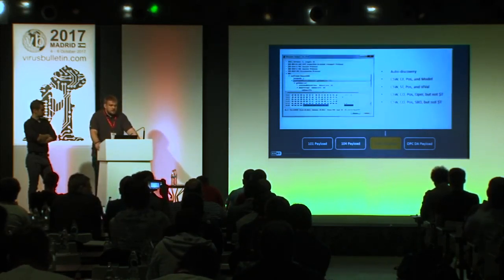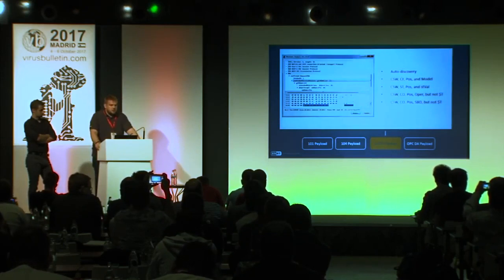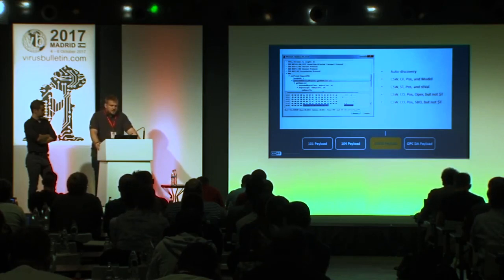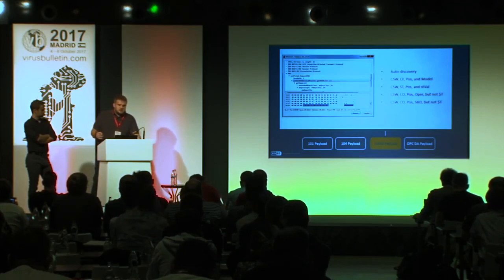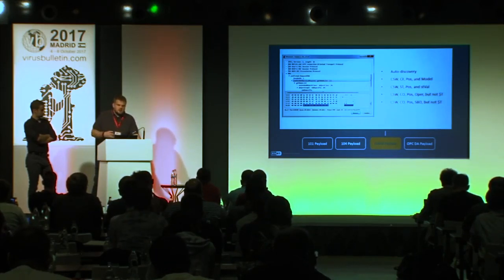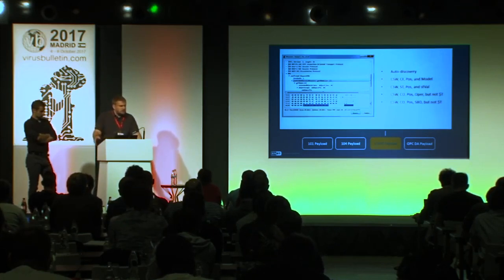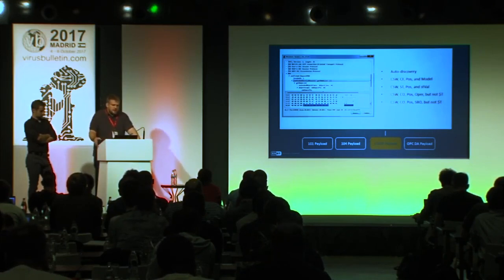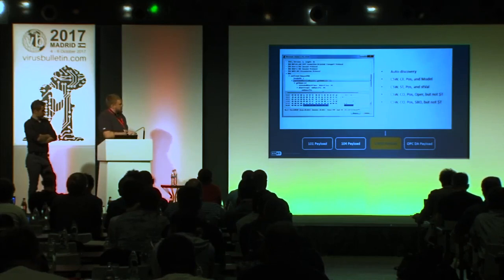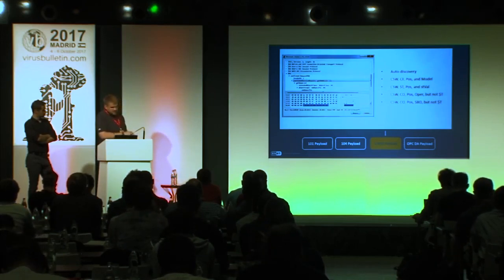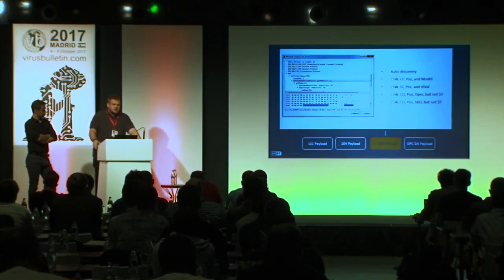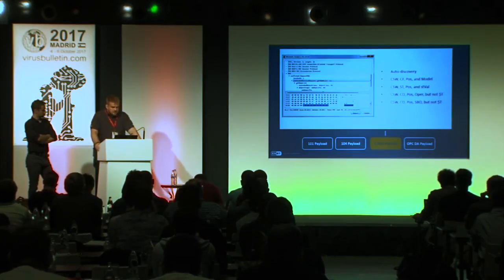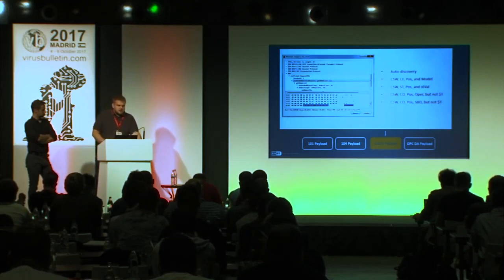61850 is a bit different and a bit more advanced. Like 104, it operates over TCP/IP, but it functions even if an IP address is not defined in the configuration. It has auto-discovery features, so it can discover these devices in the network. It does not operate on IOAs, but on named elements. It looks for hard-coded names, and they correspond to circuit breakers and switches. So it's a different approach, but the same purpose: to open or close circuit breakers.